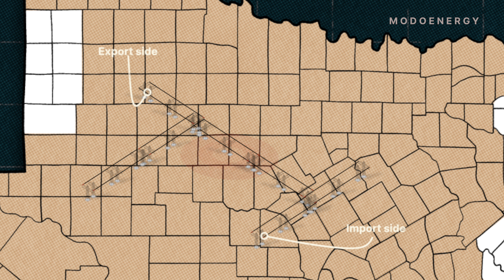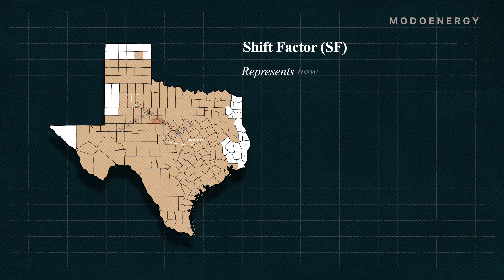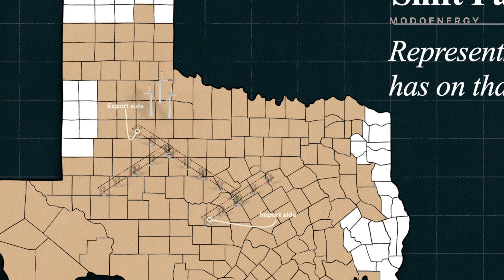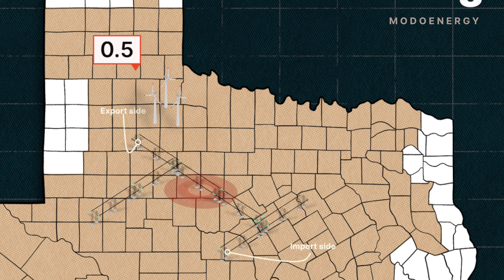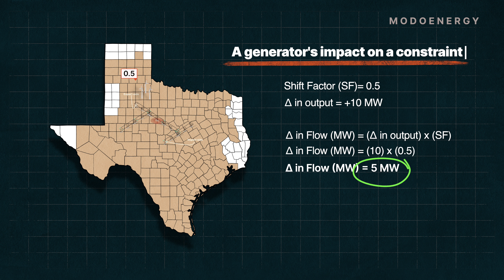For any constraint, every generation or load resource in ERCOT has what is known as a shift factor. This shift factor represents how much impact that resource has on the constraint. For example, imagine a generator close to the export side of a constraint — it might have a shift factor of 0.5, or 50%. If it increases its output by 10 MW, the flow across the constraint would increase by 5 MW.